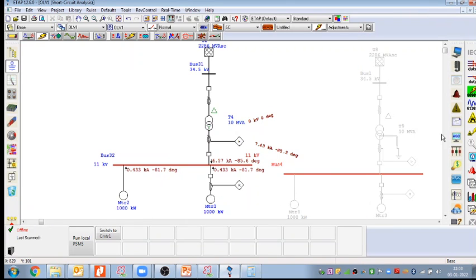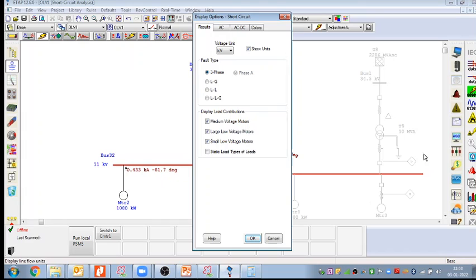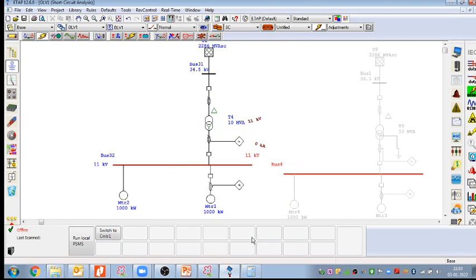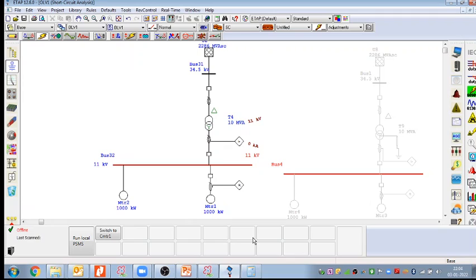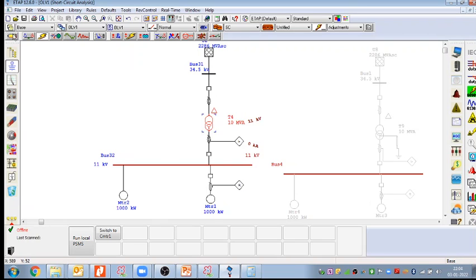Now next, let us take it if I convert this into the line to ground fault current L2G. Here we can see fault current 0 kiloampere. Since the fault happened due to the line to ground, the fault happened but it could not be sensed. It is showing 0 kiloampere. So how can we sense the fault current here? We have to provide the earthing. And this 11 kilovolt is coming again.